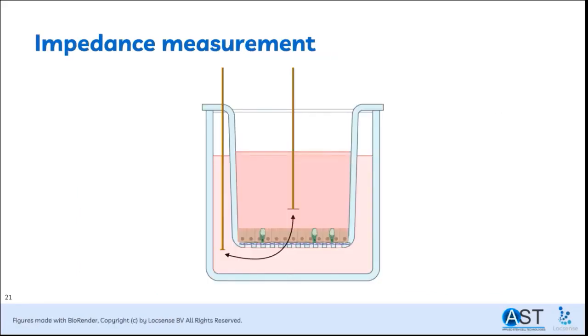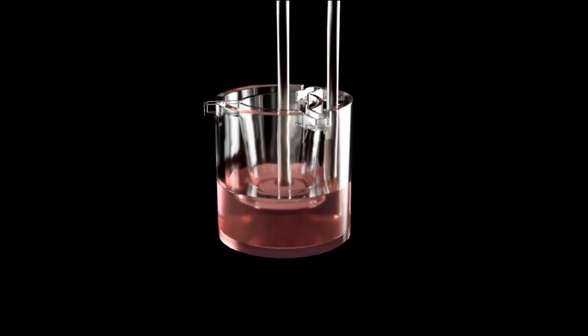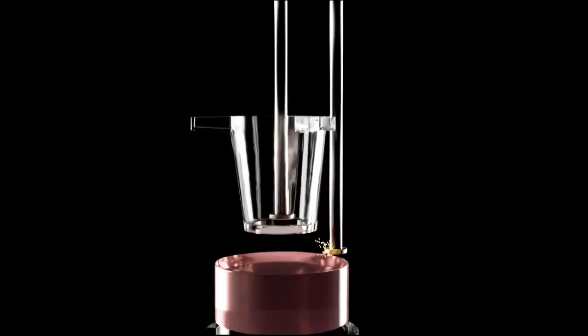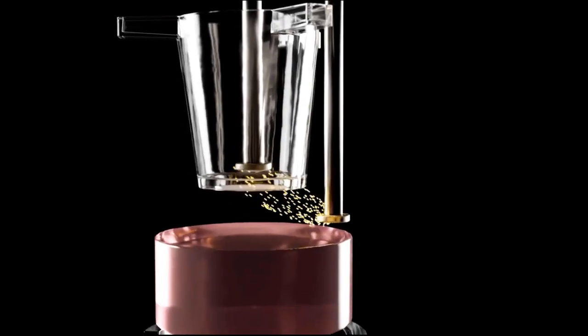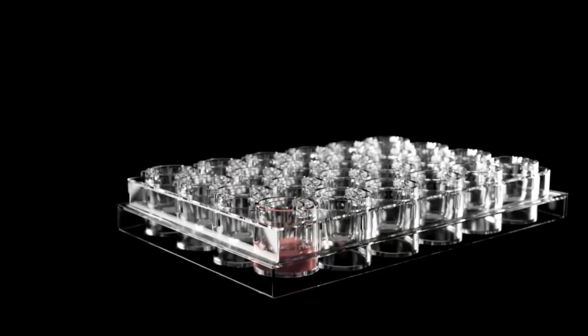Measuring the impedance is performed with a set of two electrodes: one on the apical side of the transwell and one on the basolateral side. Current flows up and down between those two electrodes, and the impedance over the whole path or circuit is measured. In an animation of the measurement, you can see a transwell-containing well, with one electrode positioned inside the transwell and the other outside. Current flows up and down through the cell layer, and the impedance of the current through the cells is measured.